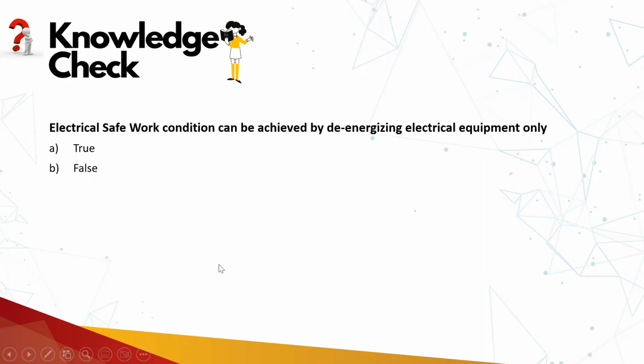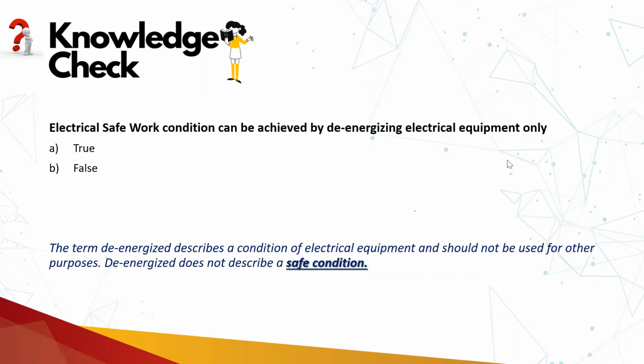The answer is B, it's false. It cannot be done if you are only de-energizing. You have to follow all Article 120.5 requirements. The term de-energizing describes a condition of electrical equipment and should not be used for any other purpose. De-energized does not describe a safe condition.